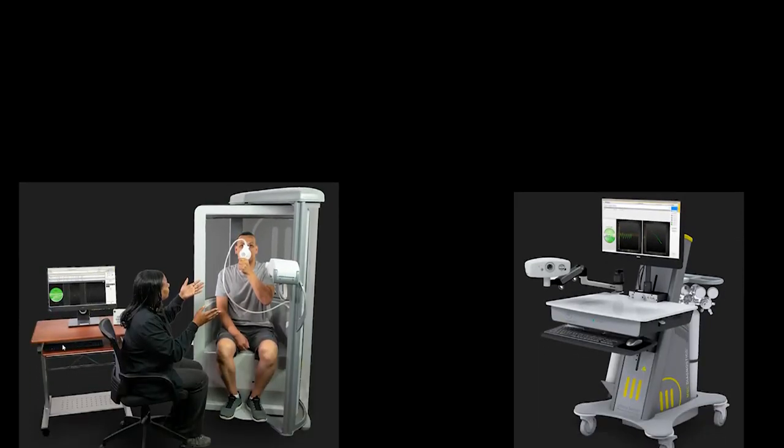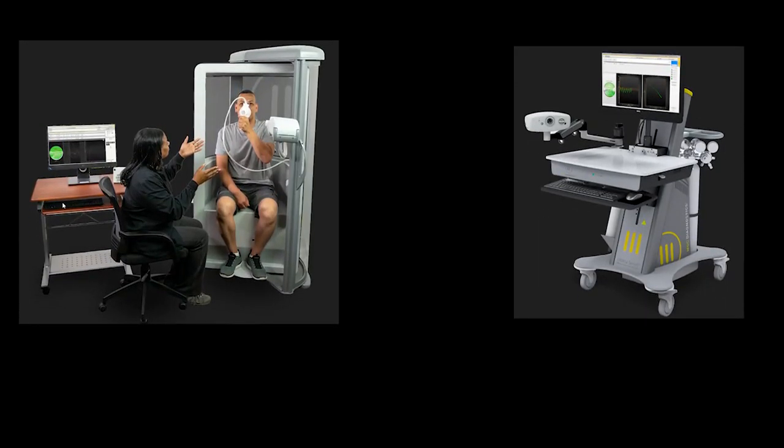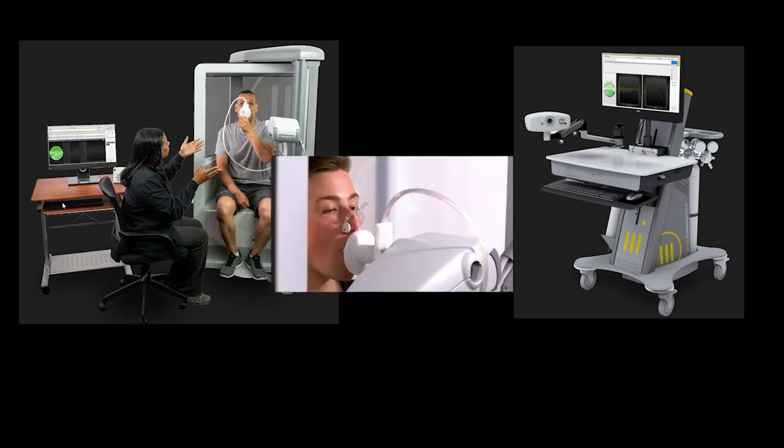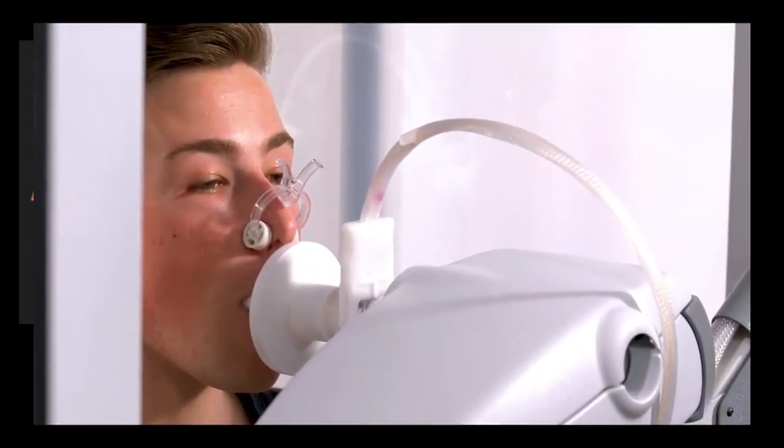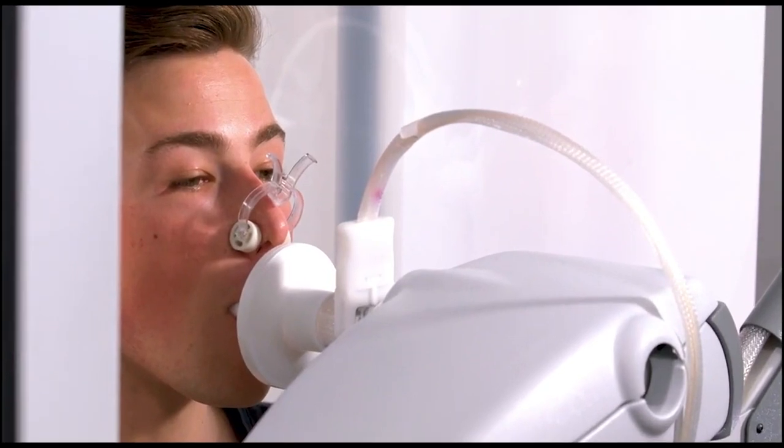While the ATS does not give a recommendation for frequency on performing nitrogen washout quality control, MGC Diagnostics recommends performing this test weekly if nitrogen washout is the main procedure used to determine lung volumes.